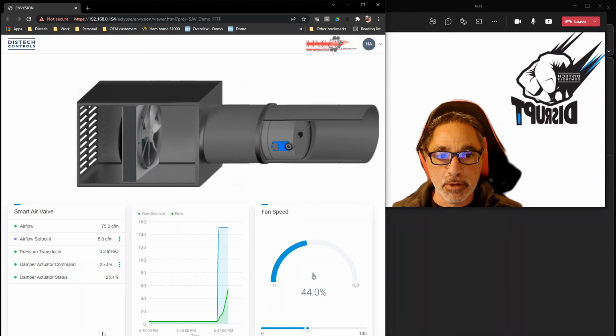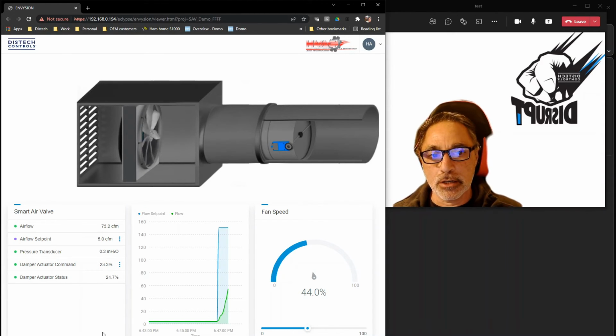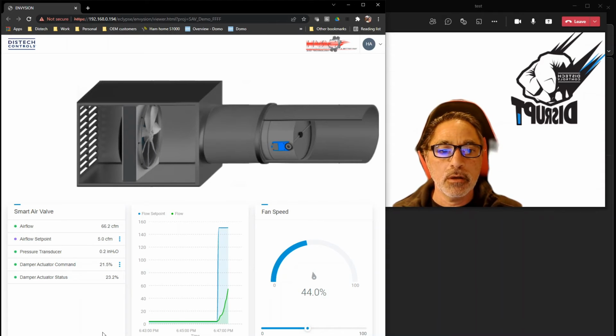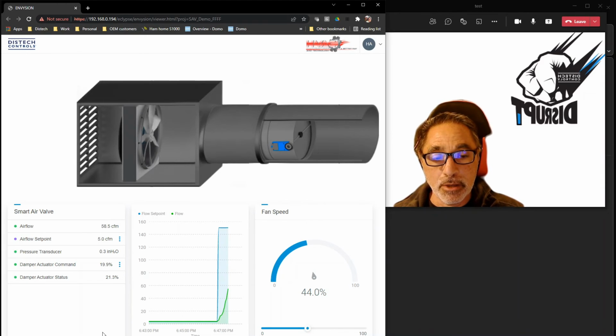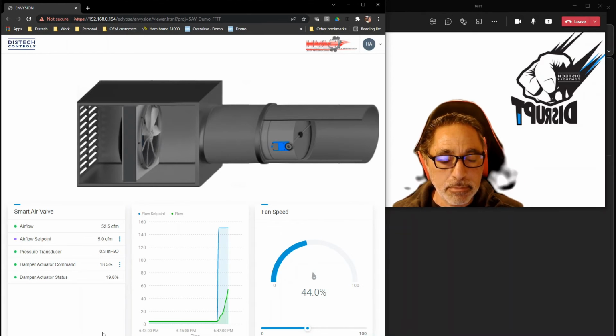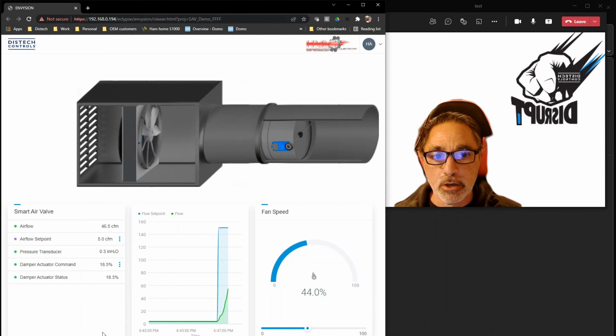Even though your unit needs to run and provide fresh air into the space, from a temperature control standpoint, you have to consider the amount of CFM you need for your zones, and as you calculate all the zones, you have to make sure you have a certain minimum requirement of CFM. Most of the time, based on those requirements, your CFM has to be very low. A lot of the traditional VAV boxes cannot get that low. So basically you have your primary equipment running harder than it should and providing more air in the space than it should.